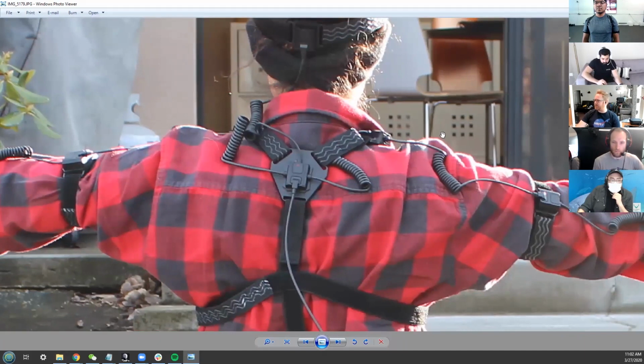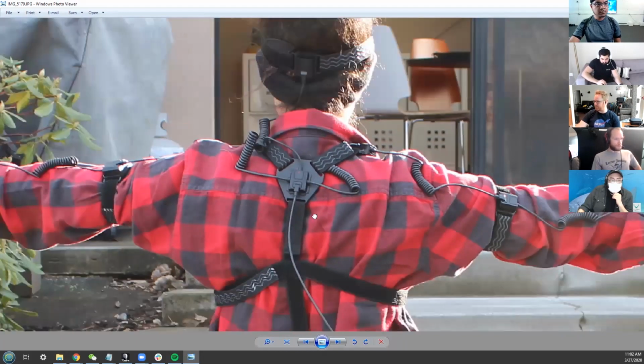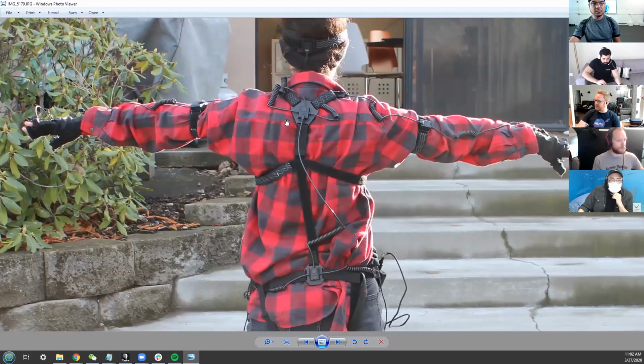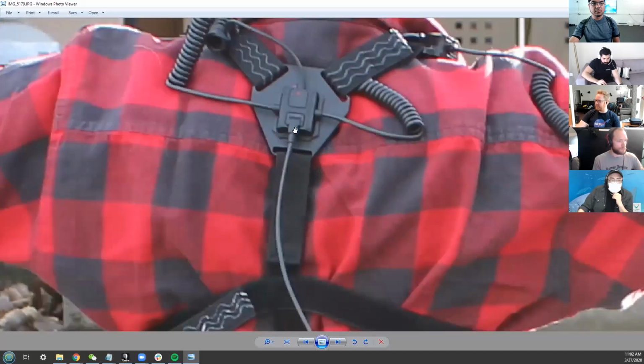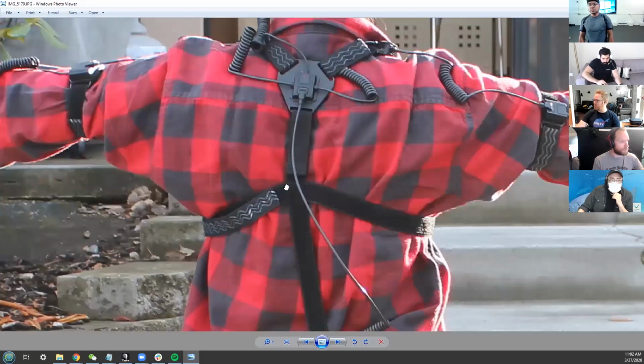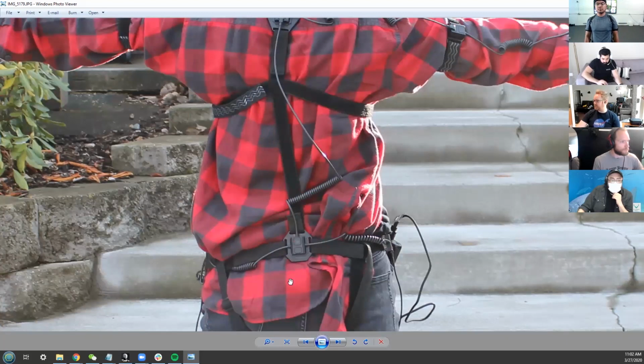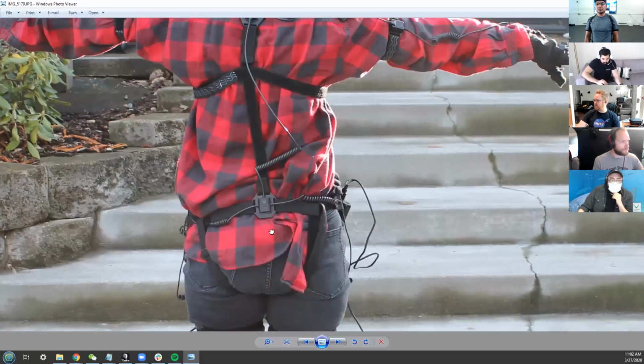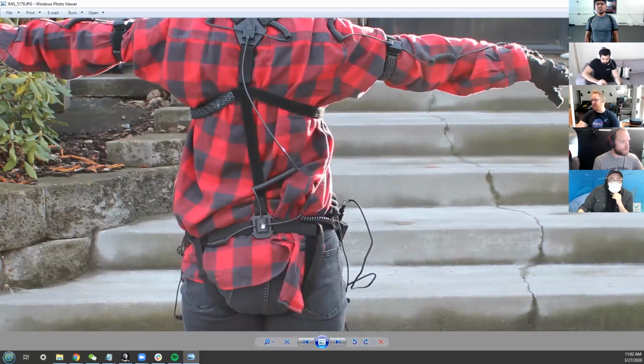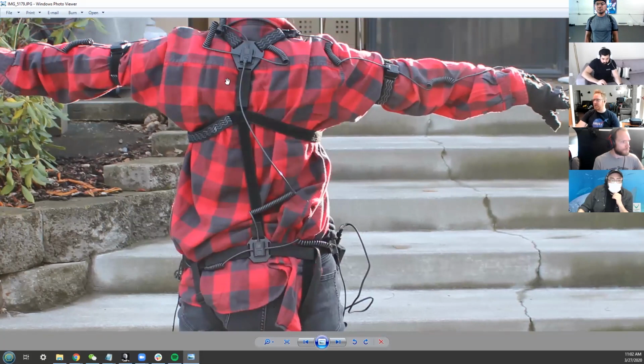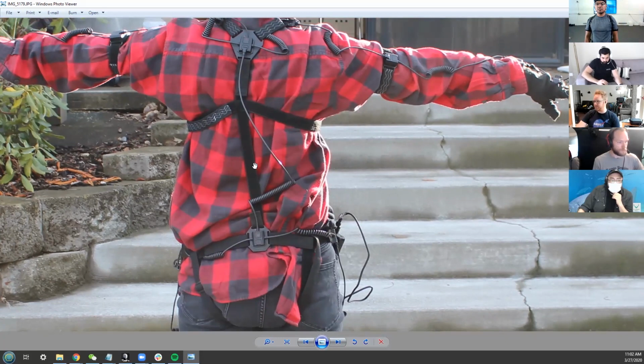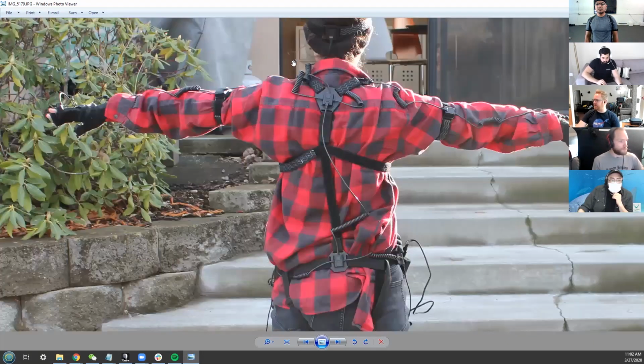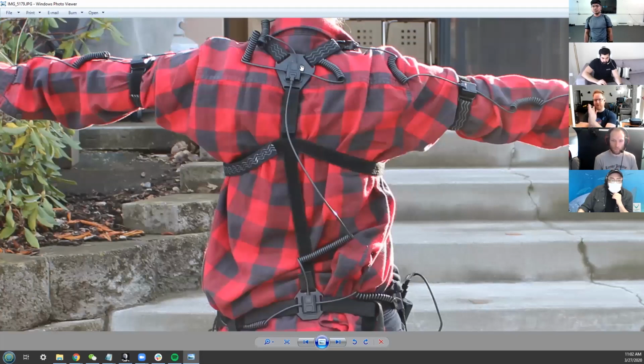In the previous picture, I pointed out that the upper back sensors had been turned into shoulder sensors. So the upper back is not preferred. But primarily, you see how the upper back sensor is turned? It's not straight vertical. It's actually cocked, I don't know, about 10 degrees clockwise. And your hip sensor is, first, too high. We're looking at about 2 inches higher than we want it to be. But the back sensor is turned. So the entire spine will have an arc to it as it starts moving, because these two sensors are twisted and not in the right place during calibration. So that's a big one. These two, the upper back and lower back, should be in perfect vertical alignment, affixed to the body.